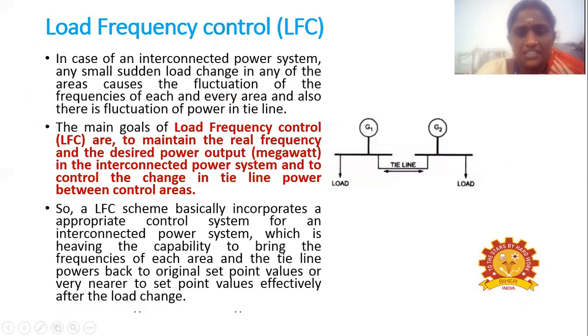First we'll see load frequency control. The main goal of load frequency control is to maintain the desired frequency and power output in the interconnected power system, and to control the change in the tie line power between the control areas. Here two generators are connected in parallel and interconnected by a tie line. The main aim of LFC is to maintain constant frequency and the desired power output, and to control the change in power in the tie line. In an interconnected power system, any small change in load in any one area, either at station A or station B, will affect the entire system: station A, station B, and the tie line.